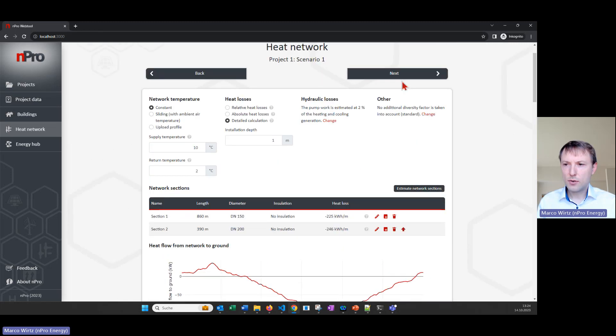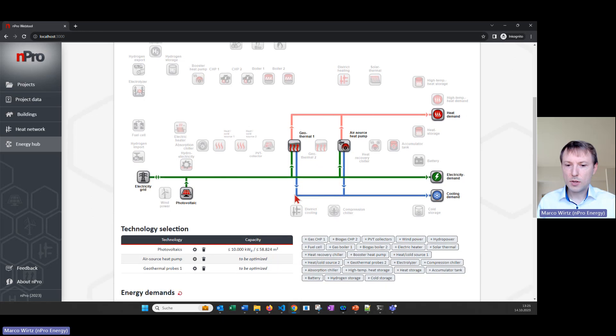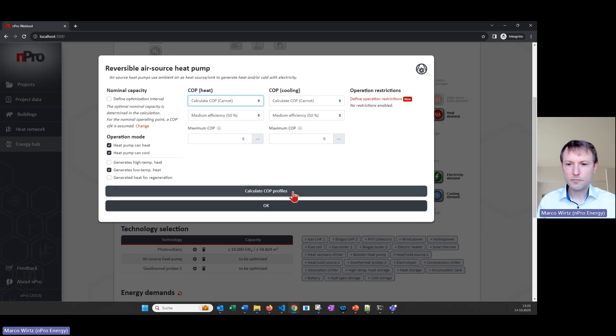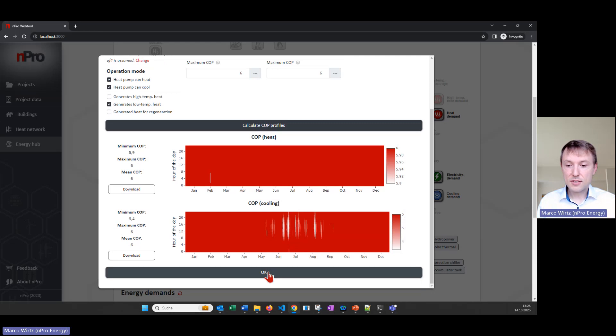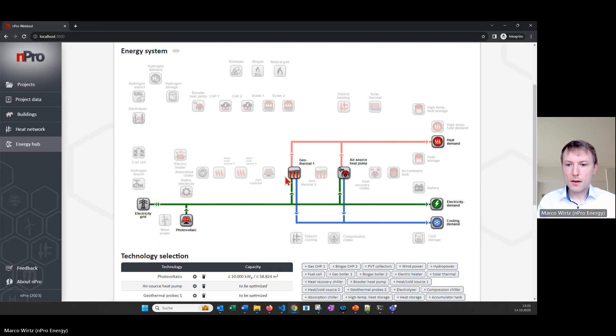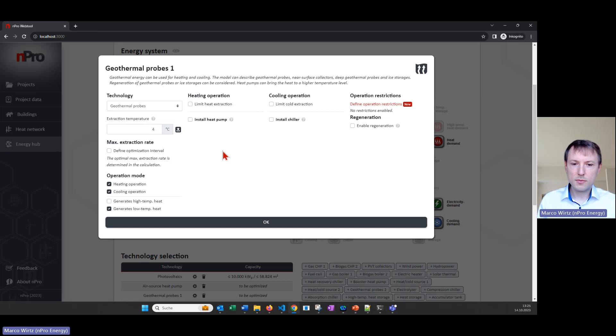Now let's define how we cover these network demands. I'll use geothermal probes and an air source heat pump. In the air source heat pump settings we can use product data, Carnot formula, or custom profiles. I click 'Calculate Profiles' to see the COP profile — because the fifth generation network has very low temperatures, the heat pump achieves very high COPs. For the geothermal entry, I deactivate the heat pump since we directly use heat from the ground to cover the fifth generation network demands.